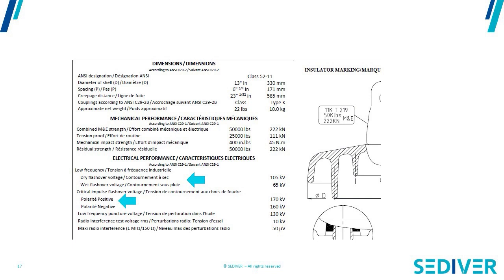The second definition is critical impulse flashover voltage. This is a voltage applied on a very short-term basis, simulating lightning. We give values in our catalogs for both impulse flashover and withstand. A lightning can have two polarities — either positive or negative — so on our drawings we give a critical impulse flashover value in both positive and negative polarity.